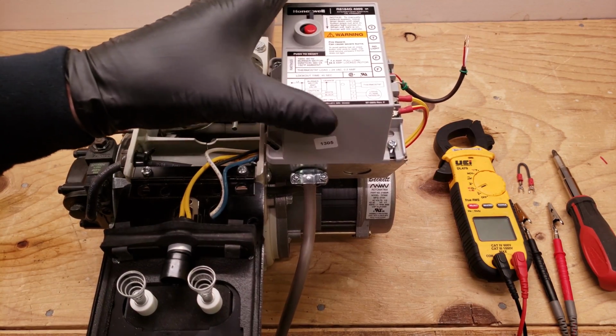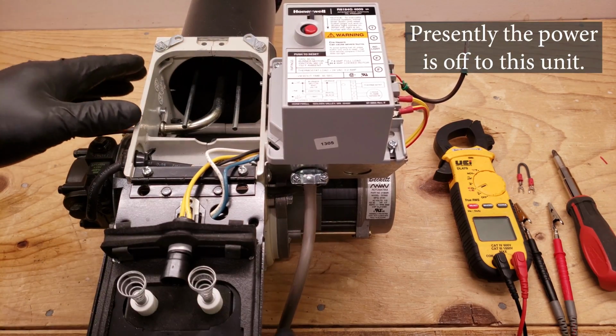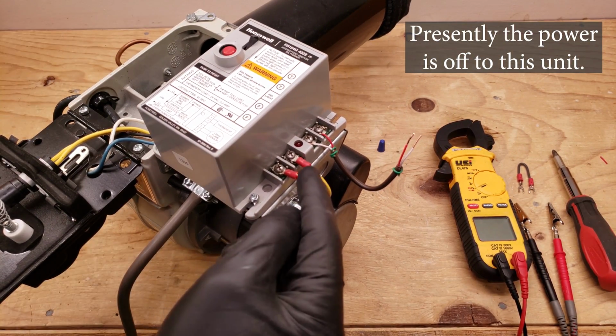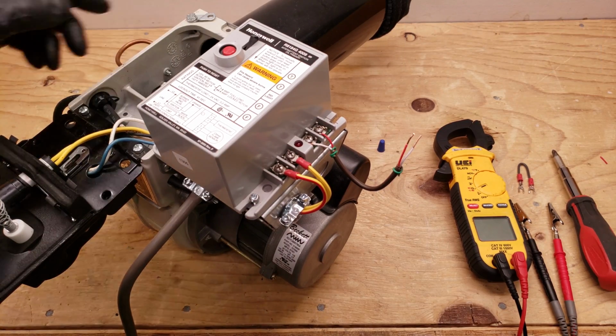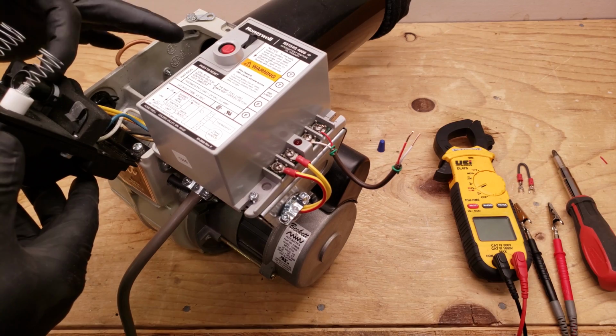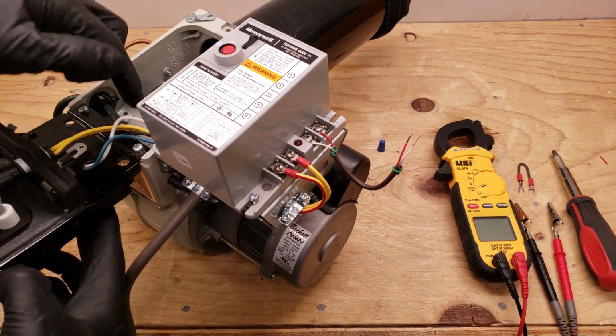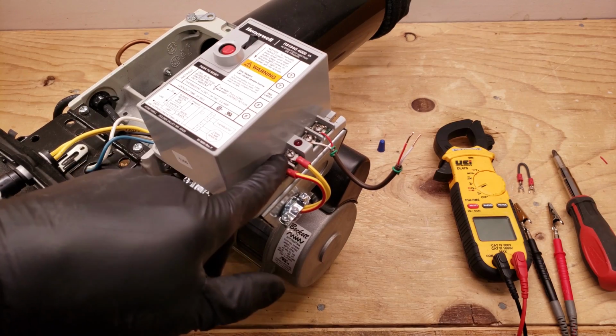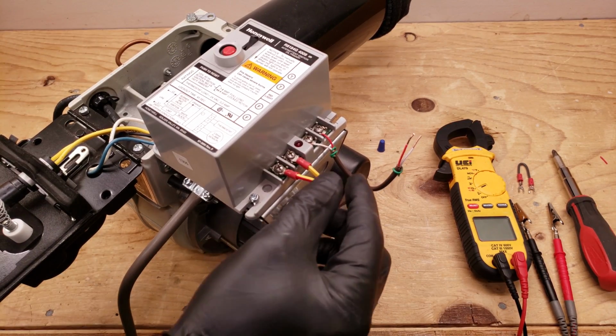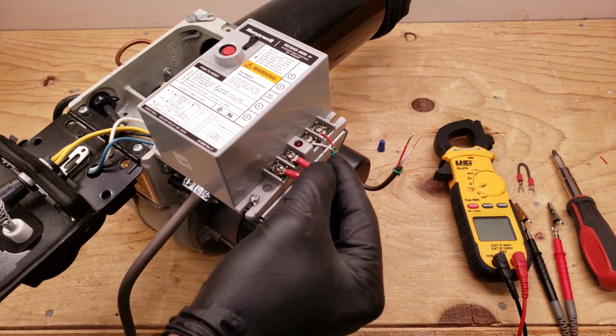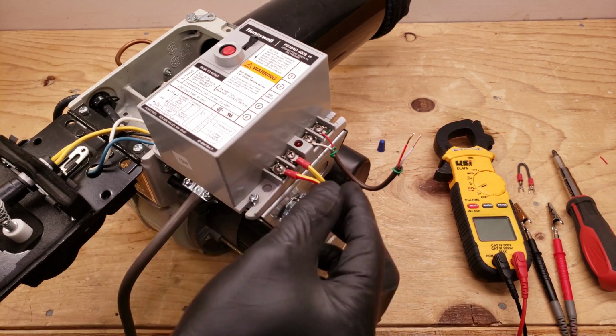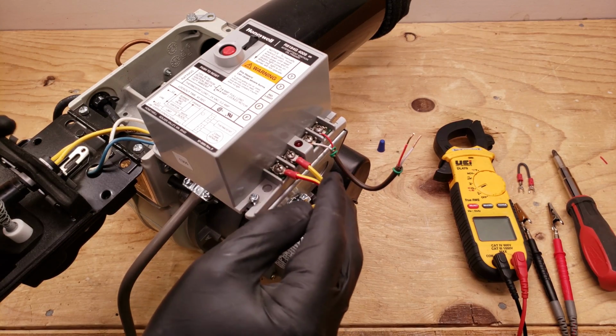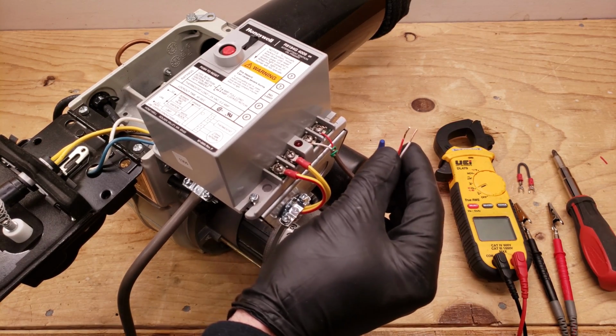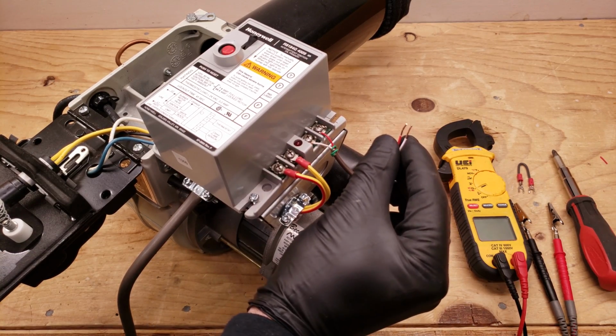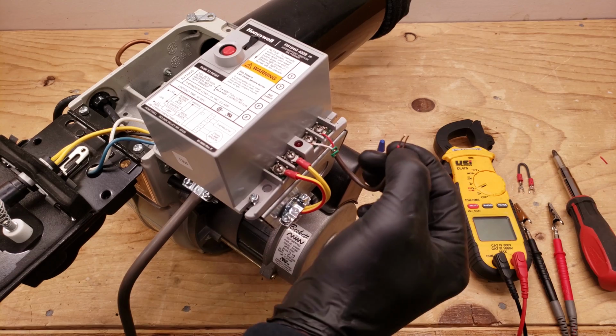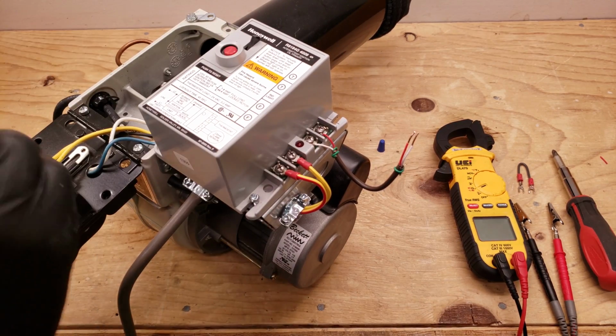So this right here is going to control the operation of the oil burner, and it needs two things. It needs to make sure that you don't already have a flame in the chamber, and it's able to tell that by the CAD cell reading coming from right here. These yellow wires come through this box down here and over to the F and F terminals. So it should have a very, very high resistance reading indicating that there is no light. When there is light, it'll have a lower resistance reading, and I'll go over those values shortly. The other thing is it has to have a signal to turn on, so the T and T terminals. Once these two wires connect right here, then this oil burner is going to go ahead and light.